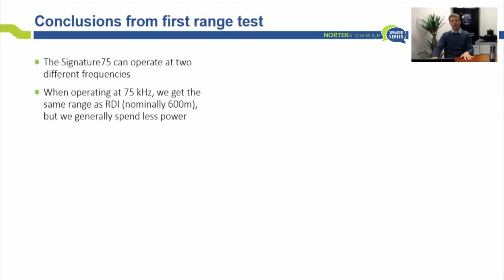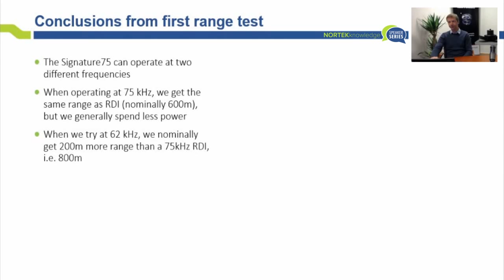Basically, we saw how many more meters do we get, how close are we—we use that as a reference, and then we use RDI specs as a reference. It may seem a little strange, but it's the only way we found to deal with this, because there's really a huge variation in the scattering in the ocean, and there's no absolute comparison unless you actually go to the point of running absolute calibration on these systems, and nobody is doing that today.